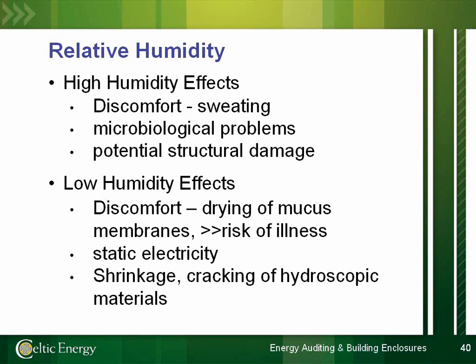Going back to moisture management, high humidity can cause discomfort for occupants and affect their ability to reject heat. It can also cause microbiological problems, since any moisture that condenses out can potentially support mold growth. The formula for mold is moderate temperatures plus water plus a nutrient. With sheetrock, the paper covering is the nutrient mold likes. If you have a high humidity condition inside with a direct thermal bridge to the back side of the sheetrock, condensation can form and result in mold growth, since mold is ever present in the air.